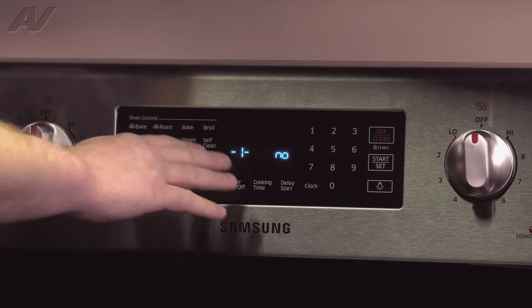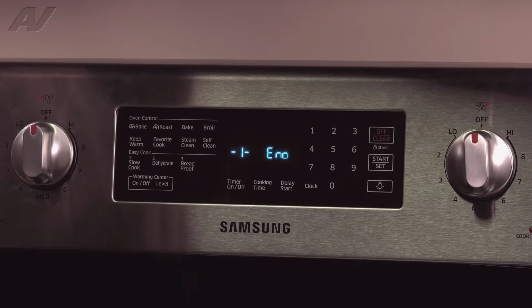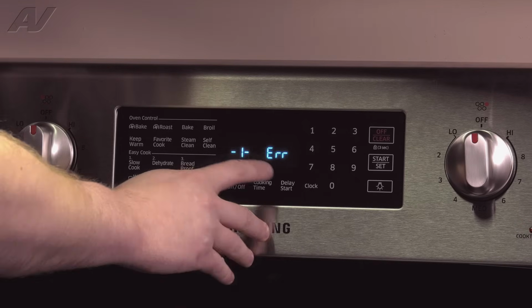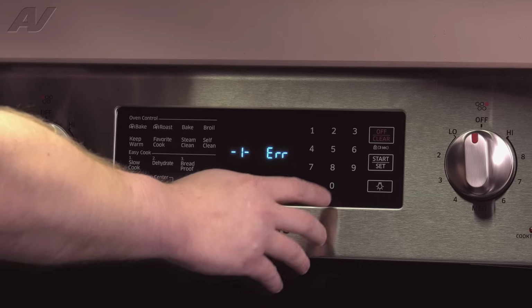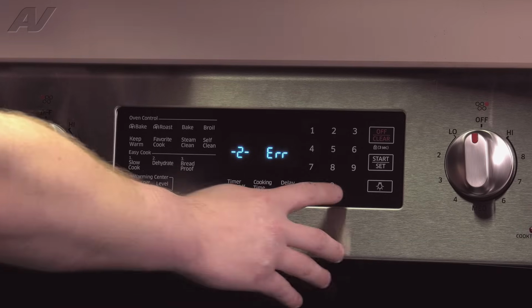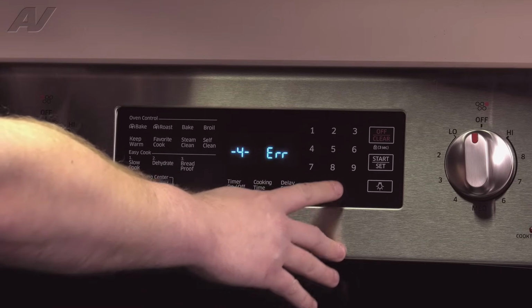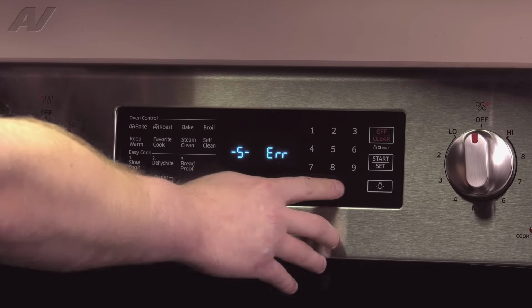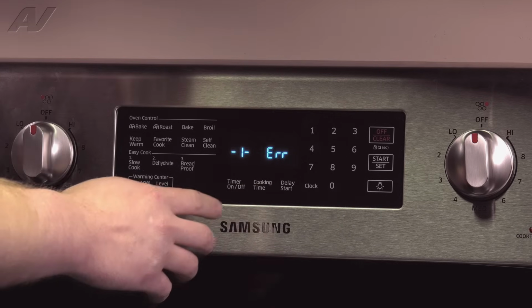Now, every time you go into this, it's going to show your most frequent or common error code first. This one is showing that we have no error code. To go to the next selection, you press 0. This is going to show the second error code that could be in there, and so on. It does go through 5 error codes and goes right back to 1.